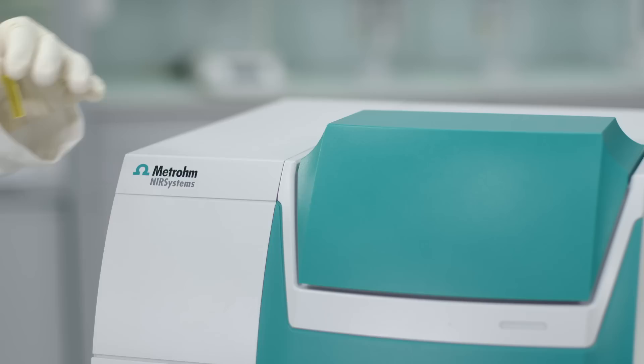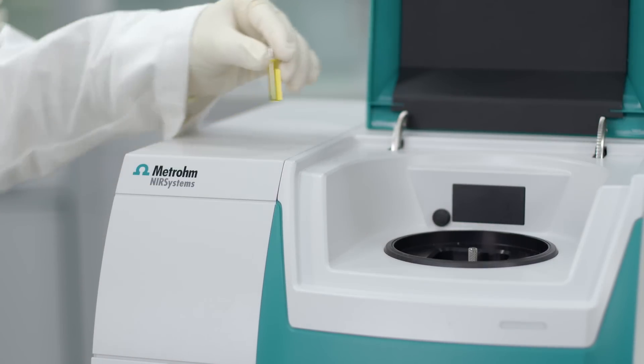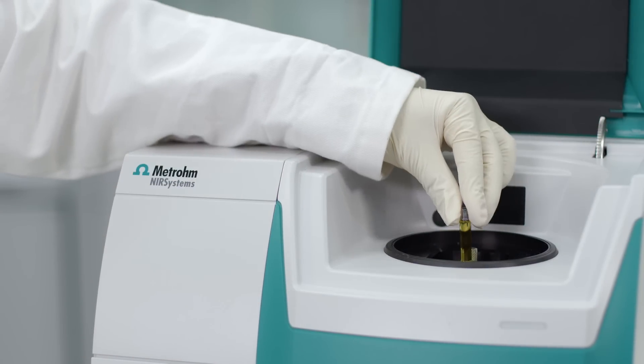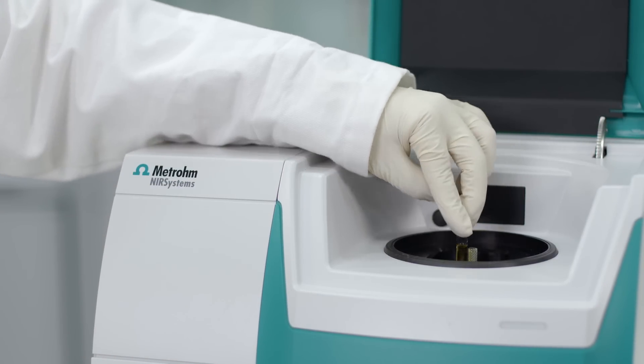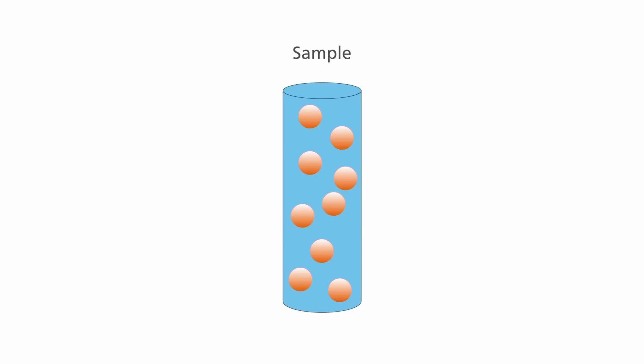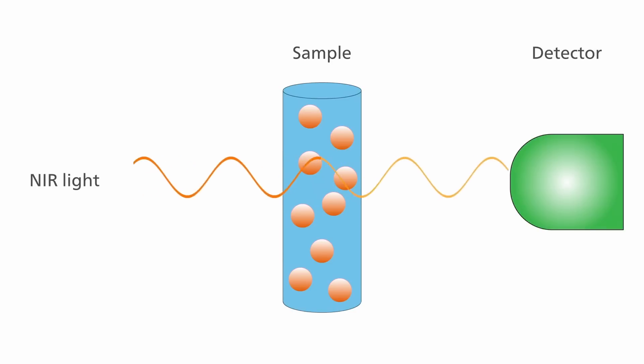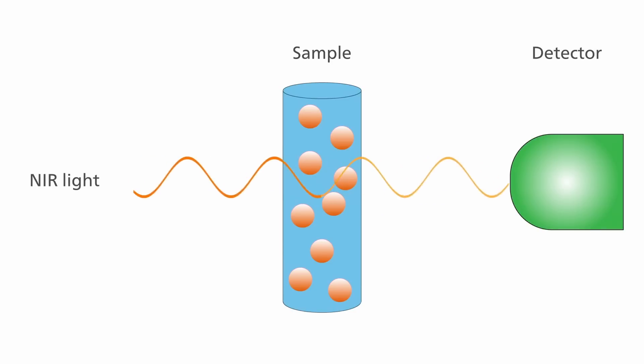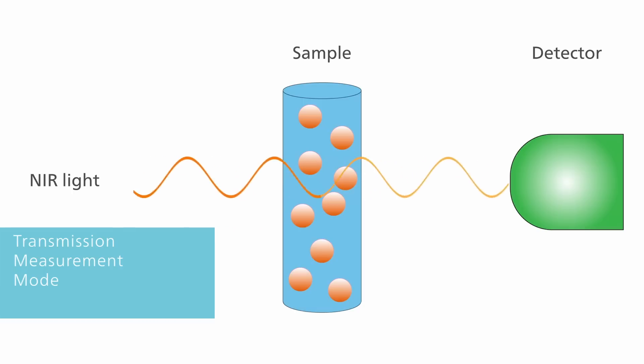For the analysis of liquid samples or suspensions, the sample is placed between the NIR light source and the detector. NIR light is transmitted through the sample, and any unabsorbed light is detected by the detector. This measuring mode is known as transmission.